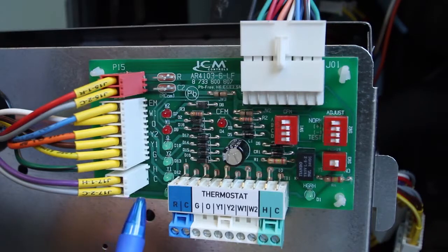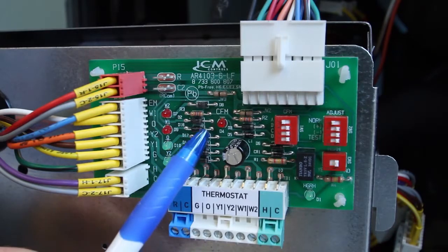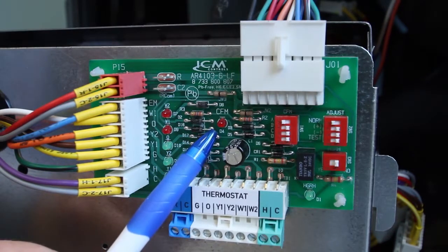Right next to those wires is a row of LEDs. You have green LEDs and red LEDs, which will be illuminated depending on the mode of operation. In the middle of the board above the terminal block, you'll see a red LED labeled CFM. This light will flash one time for every 100 CFM of air that is being demanded from the control.